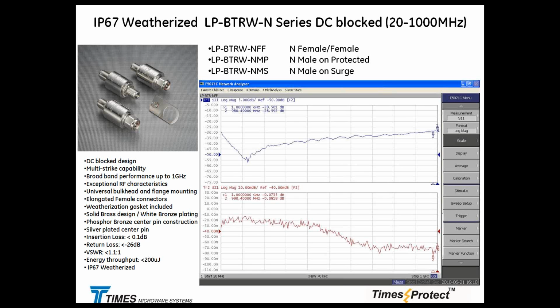Just basically, when you are selecting them, you've got to make sure that they're going to look fairly transparent to your RF. You don't want to have any issues with insertion loss or return loss, so they should be pretty transparent and come online only when needed. So pay attention to the RF characteristics and then the surge protection characteristics of every unit.